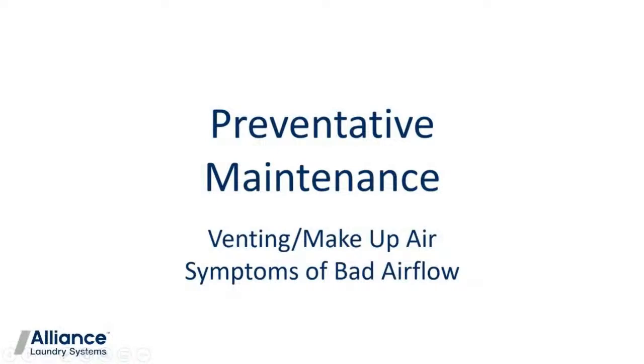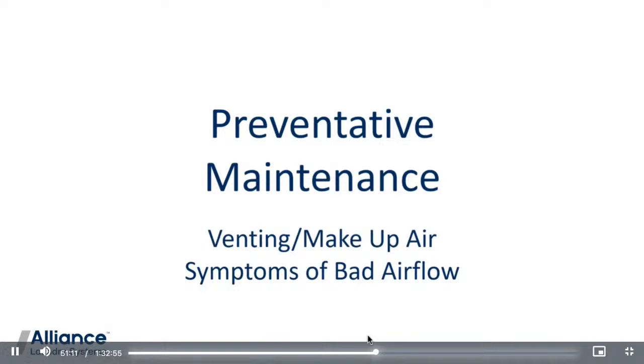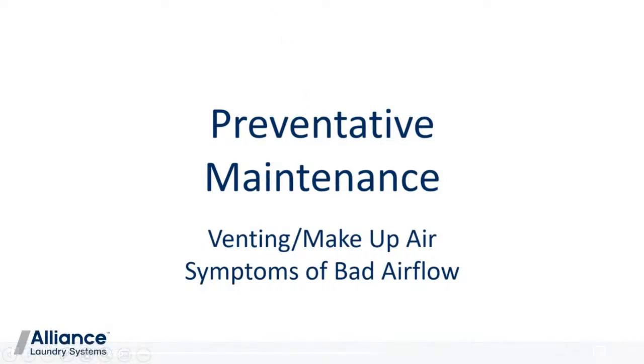So a couple things there, just so we're clear, with the video we're trying to keep it short and sweet, and I get a little fast there with my commentary. Just understanding when your venting is not good, or there's a clog, or we have too many 90s, or the run is too long, or our manifold is not adequate, the tumbler is going to try and push air through that, and the fan's going to keep running. And the only thing we can really measure is that if we keep blowing into that, eventually it's going to accumulate pressure in there. We can measure that pressure, and that's what we were doing.